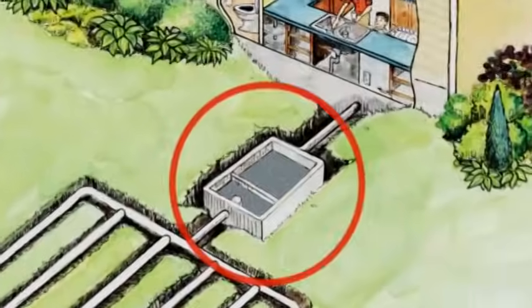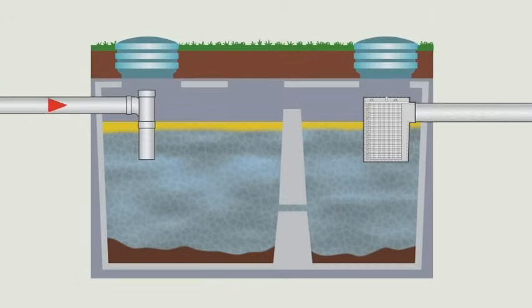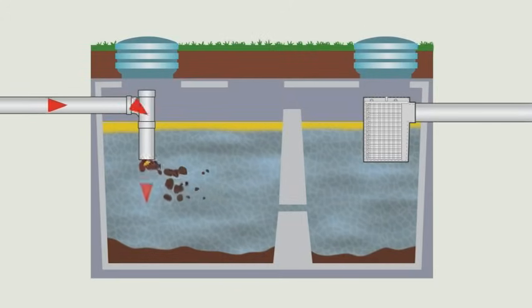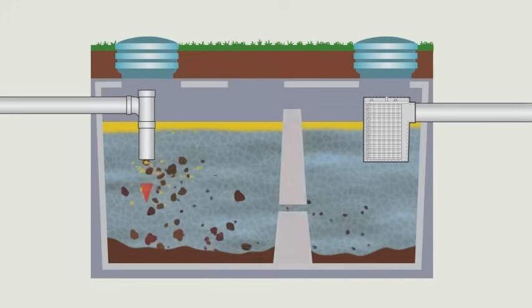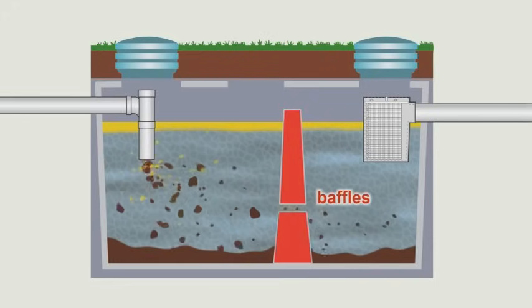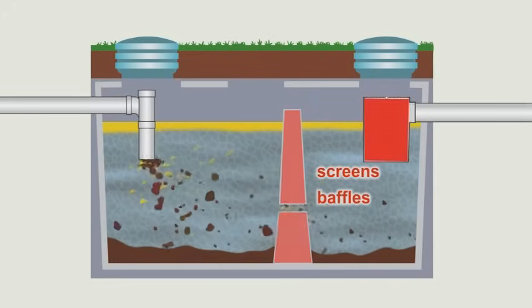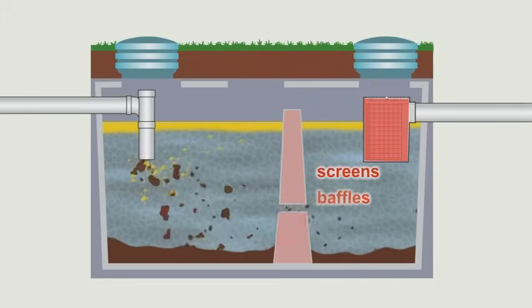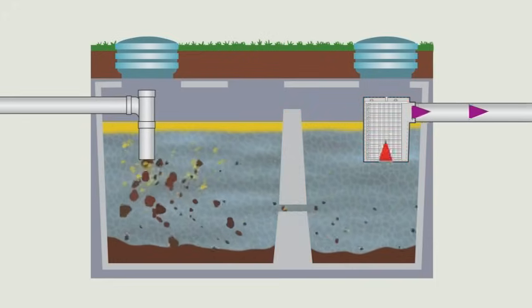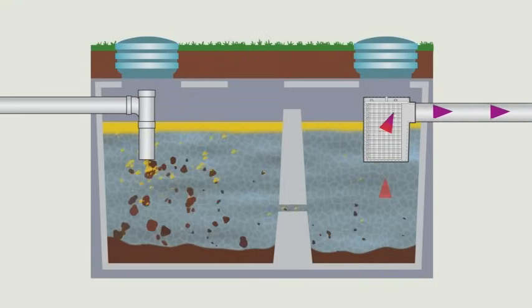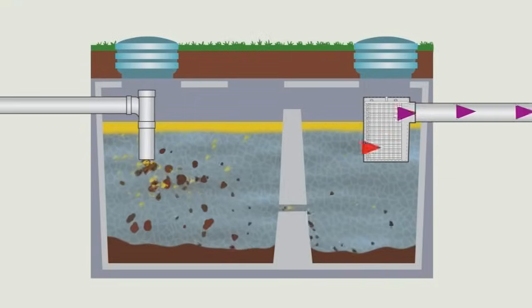The waste flows to the first compartment of the tank where the heavy solids settle, and the lighter materials — fats, oils, and greases — float to the top as scum. Baffles and screens keep this scum layer from flowing out to the leaching bed. The scum is removed when the tank is pumped out during regular maintenance.